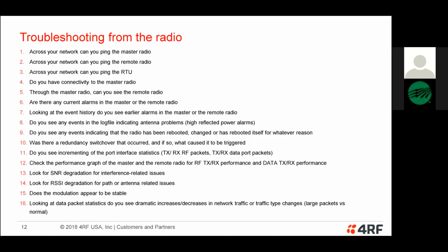The next thing to try is to ping a remote. If you can ping a master but can't ping a remote, it helps narrow down where the problem is. If you can ping the remote radio, can you ping the RTU if it has an Ethernet connection on it? It's not unusual for us to sometimes see bad RTUs that people think is a bad radio. These are all things you'd do in order of importance.